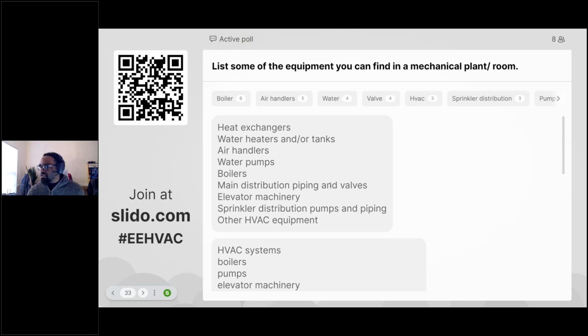You're going to lose a lot of efficiency due to leaks in your piping system and valves, especially any type of valve that still has pneumatic actuators operating on it, which may have issues. You still have a couple of applications in the field that utilize pneumatic systems as far as controls are concerned, because sometimes these systems are explosion-proof applications. So they have to continue to use pneumatic controls instead of the newer DDC model, which is direct digital controls, what your BAS systems are based on. So yes, piping is extremely important.